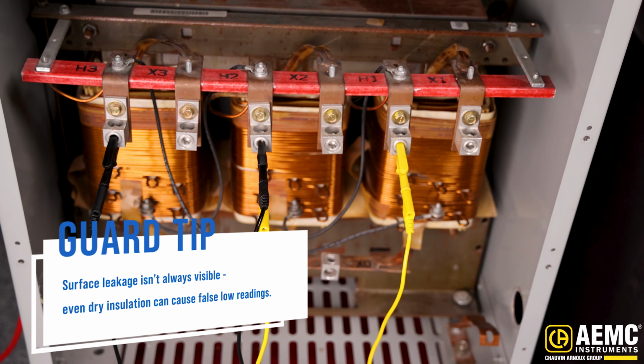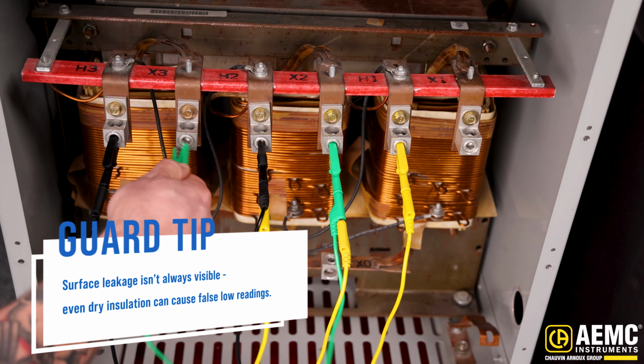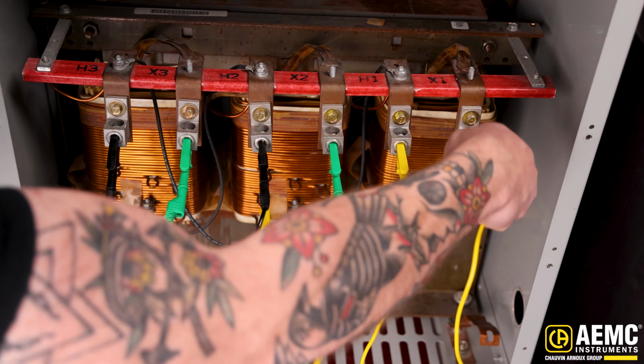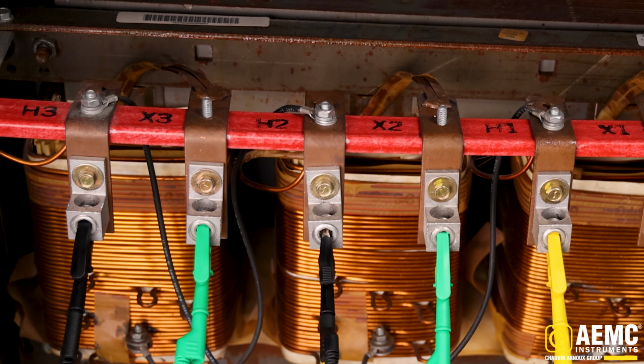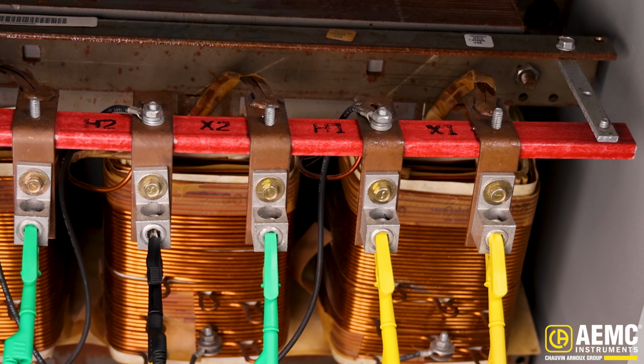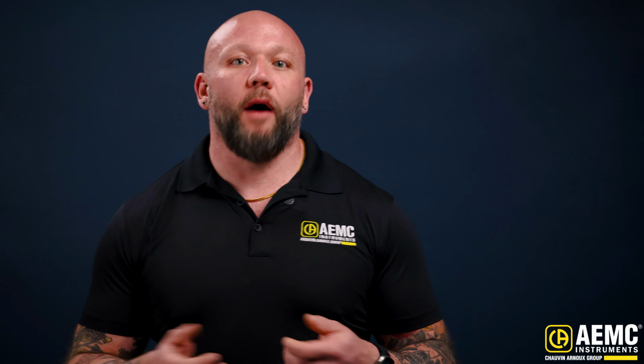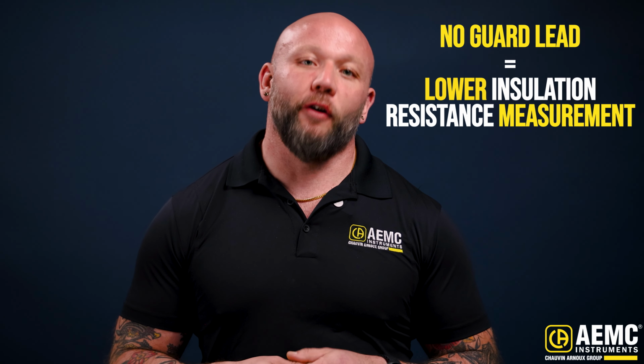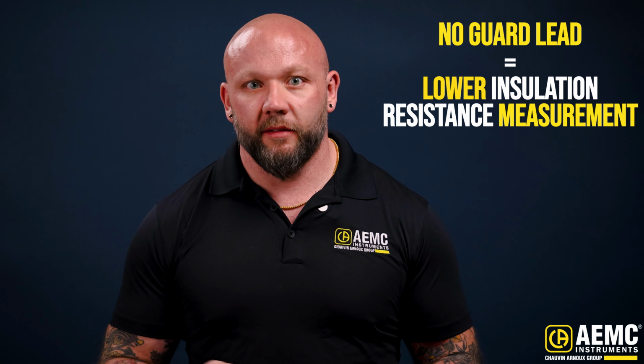Say you're testing the primary winding's insulation resistance to ground. Even if this insulation is good, current could track along the surface, especially between the windings. Without the guard, the measured insulation resistance will be significantly lower. Here's how to guard against that, literally.